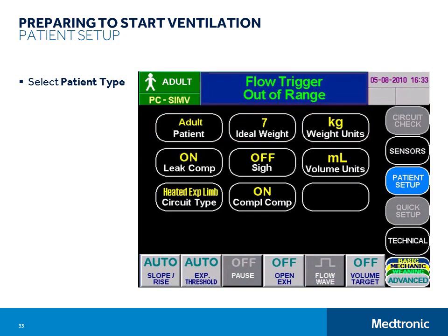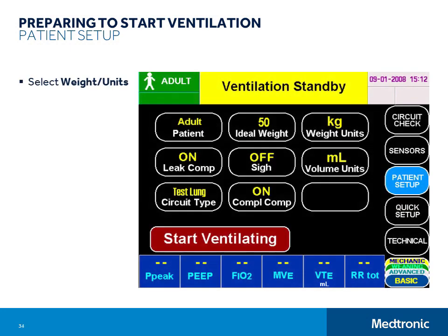The next step is to select weight units and weight. If you intend to use the quick setup function for determining startup ventilation alarm settings, you will need to enter the patient's ideal body weight, which is calculated from their height and gender, and select the weight units in pounds or kilograms. If you do not intend to use the quick setup function, you can skip this step. If you have entered an ideal body weight, you can also choose to display exhaled tidal volume numeric displays in mLs per kilogram instead of mLs.